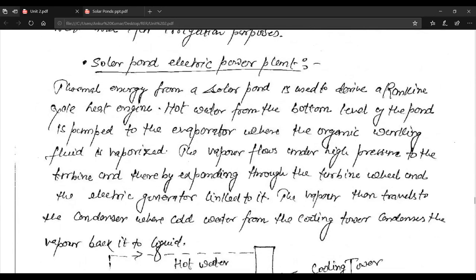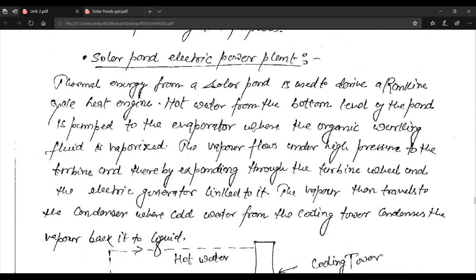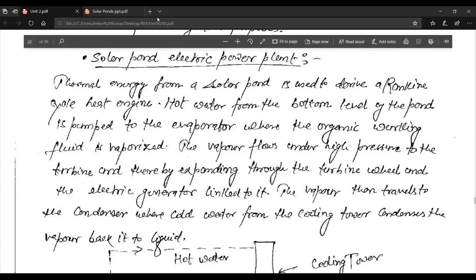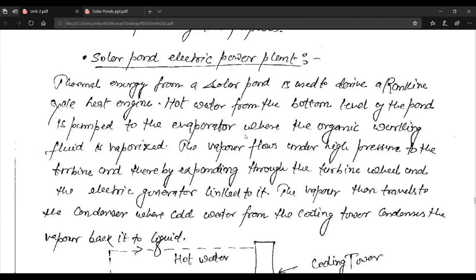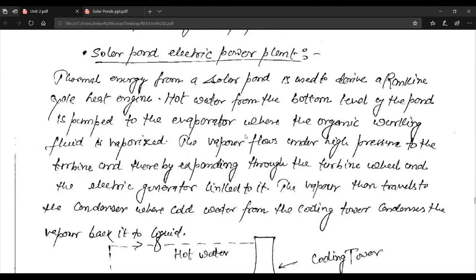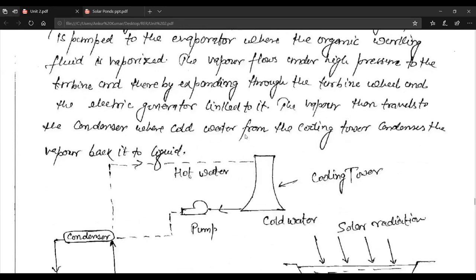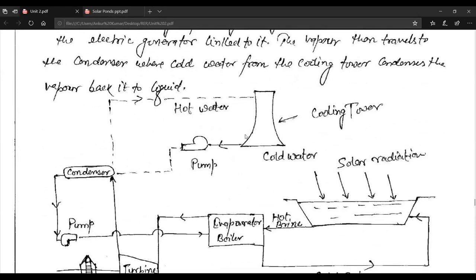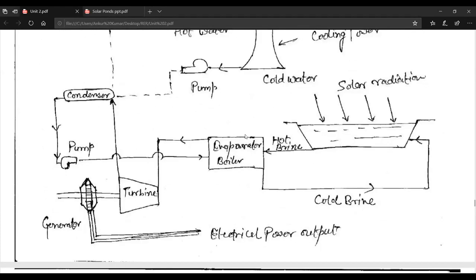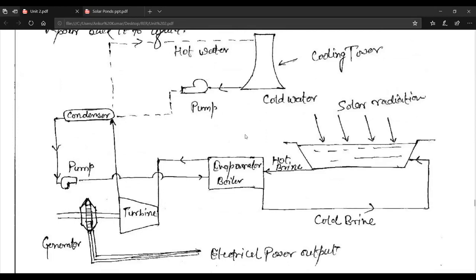In a solar pond electric power plant, thermal energy from a solar pond is used to drive a Rankine cycle heat engine. Hot water from the bottom level of the pond is pumped to the evaporator where the organic working fluid is vaporized. The vapor flows under high pressure to the turbine, expanding through the turbine wheel connected to an electric generator. The vapor then travels to the condenser where cold water from the cooling tower condenses it back to liquid.